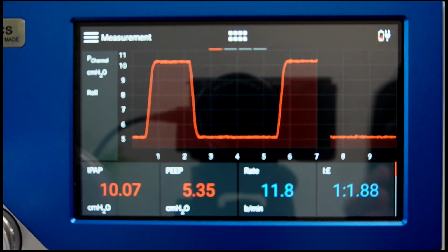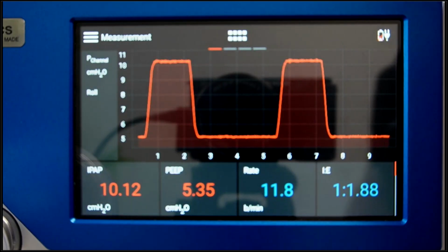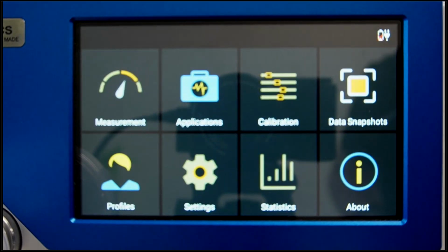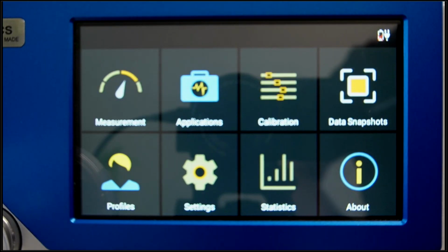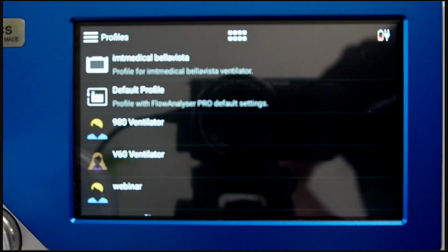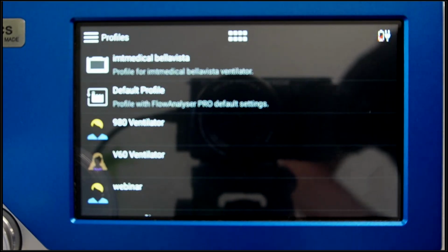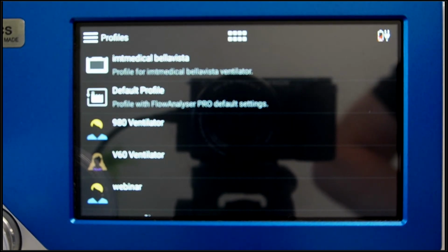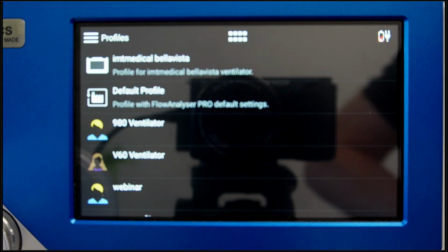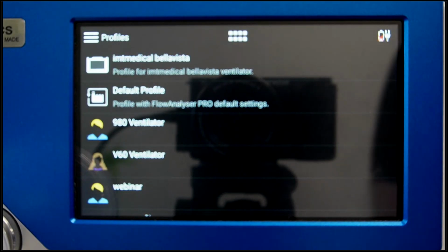And all these customizations on this device, for example, I can save as profile. So whenever I have a specific application, for example, a specific ventilator, and I've gone through the exercise of figuring out what gas standard, what trigger settings I have to use, once I configured all my screens exactly as I want to, I can then save that and name it as a profile. And next time when I have the same application again, I can just reload this profile and everything is set up the same again. So using profiles helps minimizing the risk of inappropriate settings and reading errors.